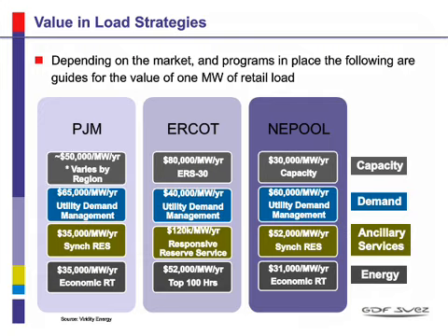So what this actually says is that in PJM, for example, participation in a capacity program, traditional demand response, depending on the year and the region, is in the neighborhood of about $50,000 a megawatt per year. So if you have a 5-megawatt load and you're willing to nominate or bid in up to 1 megawatt of load reduction at certain times when the ISO calls for it, they'll pay you a standby fee of about $50,000 a year to do that.